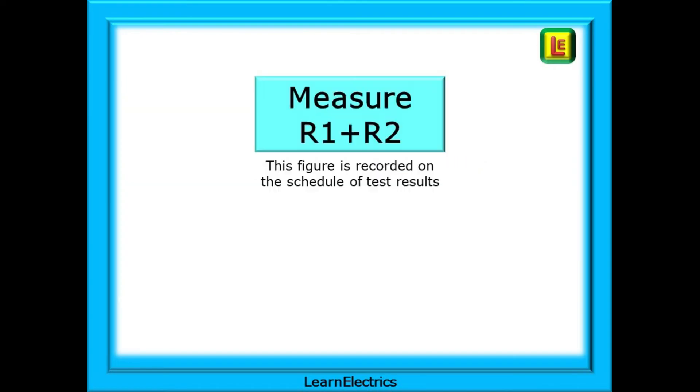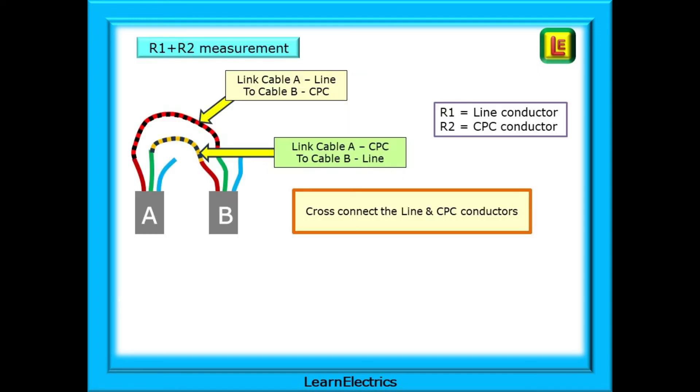If all is okay, we can now move on to measuring big R1 plus big R2. This figure is recorded on the schedule of test results, and it is important to get it right. Return to the consumer unit, and this time we must cross-connect the line and CPC conductors. Link cable A line to cable B CPC, and link cable A CPC to cable B line.